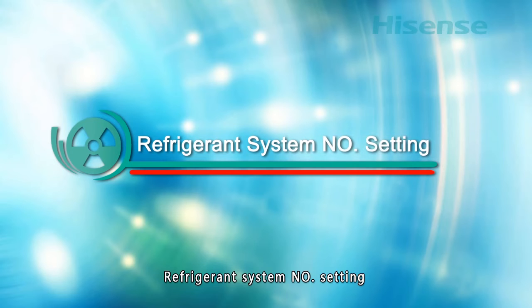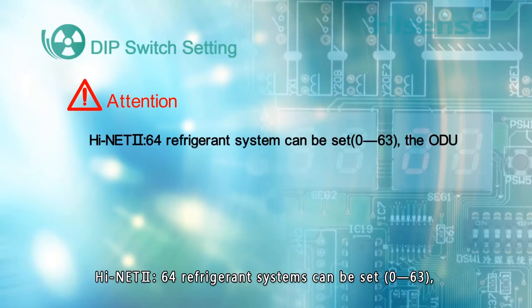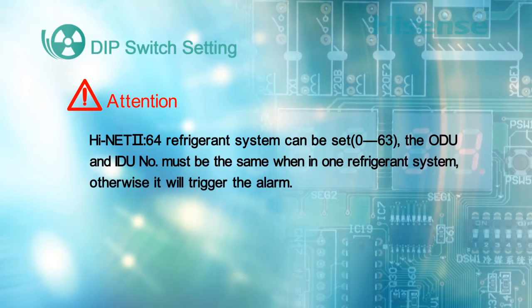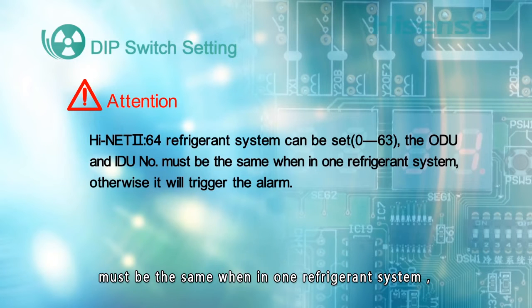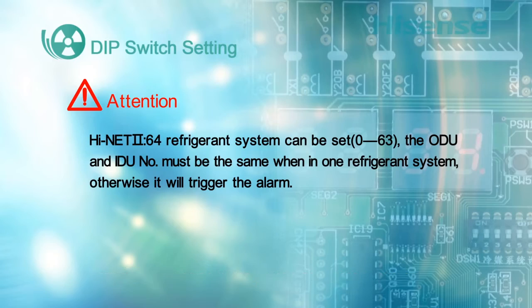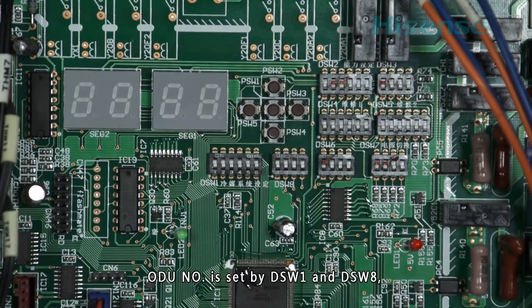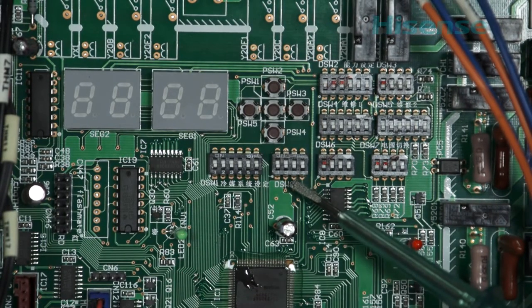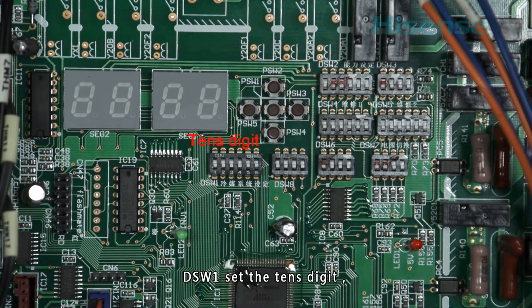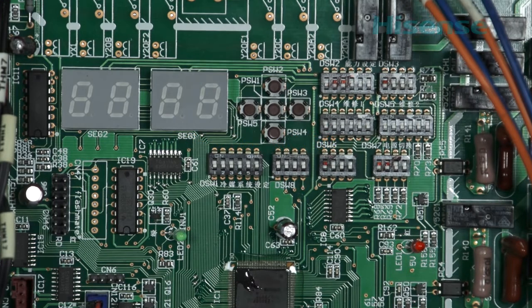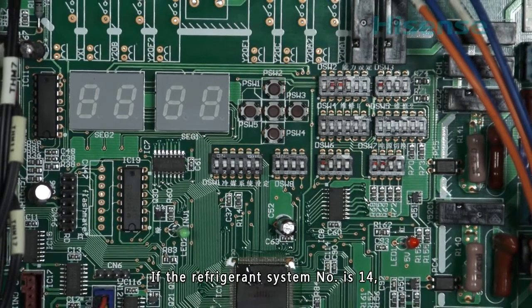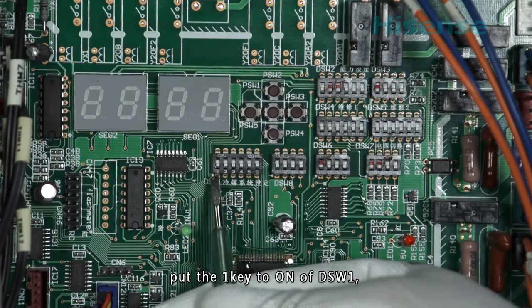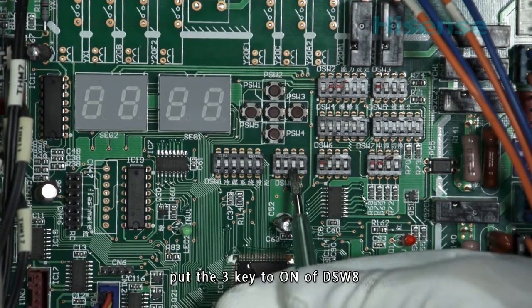Refrigerant system number setting. HyNet 2, 64 refrigerant systems can be set. The outdoor unit and indoor unit number must be the same when in one refrigerant system. Otherwise, it will trigger the alarm. Outdoor unit number is set by DSW1 and DSW8. DSW1 set the tens digit. DSW8 set the unit digit. The setting of DSW8 adopts binary arithmetic. Example: if the refrigerant system number is 14, put the 1 key to on of DSW1. Put the 3 key to on of DSW8.